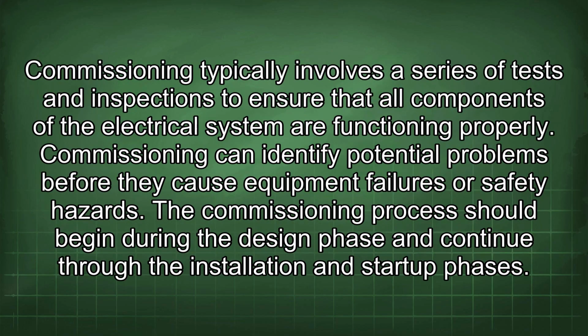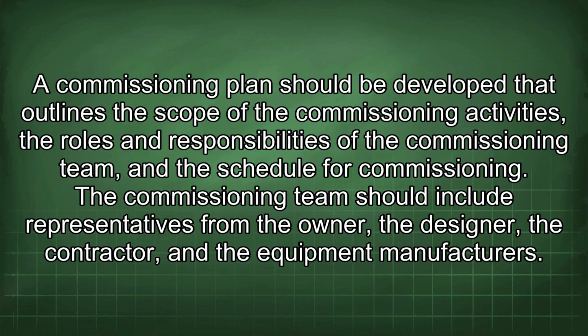Commissioning typically involves a series of tests and inspections to ensure that all components of the electrical system are functioning properly. Commissioning can identify potential problems before they cause equipment failures or safety hazards. The commissioning process should begin during the design phase and continue through the installation and startup phases. A commissioning plan should be developed that outlines the scope of the commissioning activities, the roles and responsibilities of the commissioning team, and the schedule for commissioning. The commissioning team should include representatives from the owner, the designer, the contractor, and the equipment manufacturers.